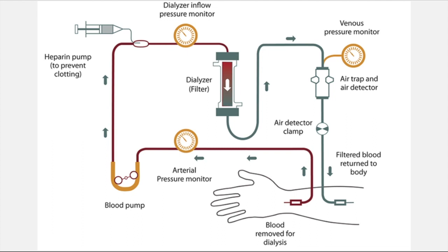Additionally, ultrafiltration is done within this system by having the solutes sweep through the membrane pores along the dialysate in response to a transmembrane pressure gradient. So the principles of diffusion, osmosis, and ultrafiltration occur within this system.